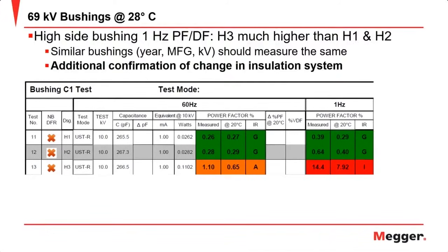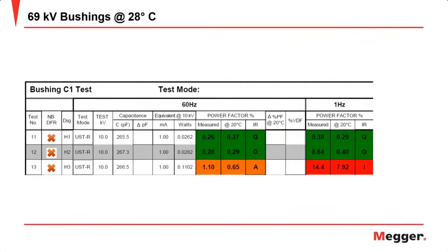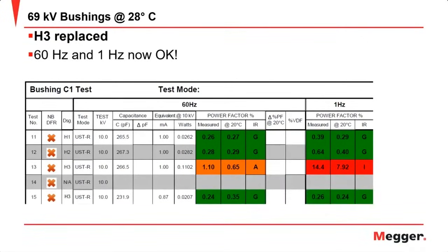So then, this customer determined that yes, this bushing needs to come out immediately. This transformer is at risk of failing due to this bushing. So they replaced the H3, and what they saw is that the 60 hertz and the 1 hertz of this new bushing that was put into place, they were also good. So again, using that information from the first 3 tests, seeing that they had 2 good bushings, they also measured low at 1 hertz, and they saw with this new bushing after it was installed that it was low at 60 hertz and low at 1 hertz.